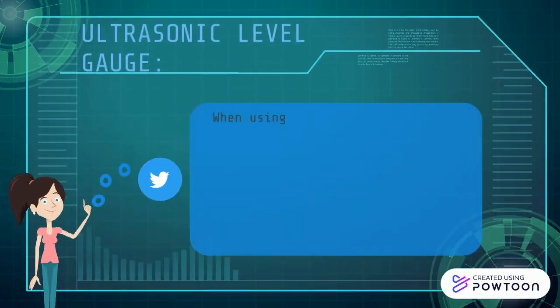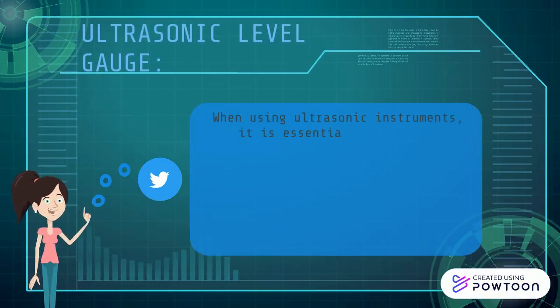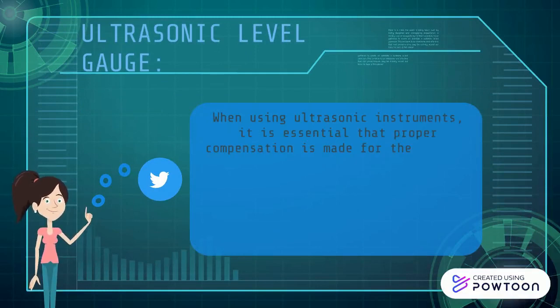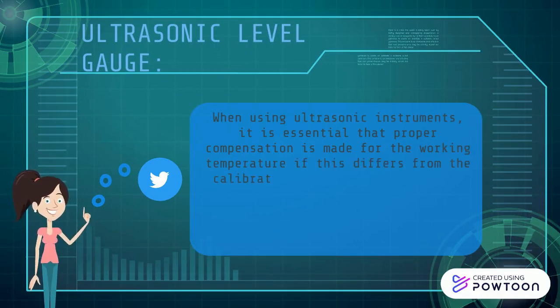When using ultrasonic instruments, it is essential that proper compensation is made for the working temperature if this differs from the calibration temperature. Since the speed of ultrasound through air varies with temperature, temperature compensation can be achieved in two ways.